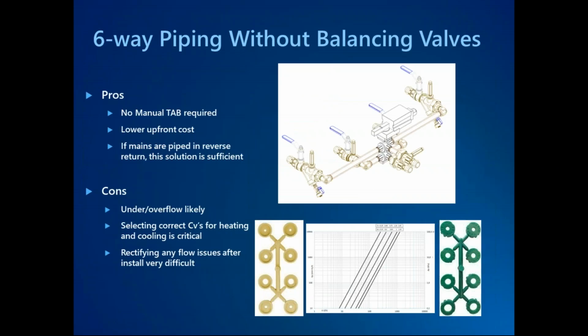So from here, for the next few slides, I want to look at some different six-way assemblies that incorporate different types of balancing valves and the pros and cons of those. Because again, the six-way is just going to either provide on-off flow control or modulating flow control for heating and cooling. We need to bracket that with some additional components in order to make sure that we're getting the performance we want. So it is possible to omit all balance valves entirely and rely purely on the CV discs, or the CV preset CV values for the six-way. Not the most recommended solution, but it will provide the lowest upfront cost.